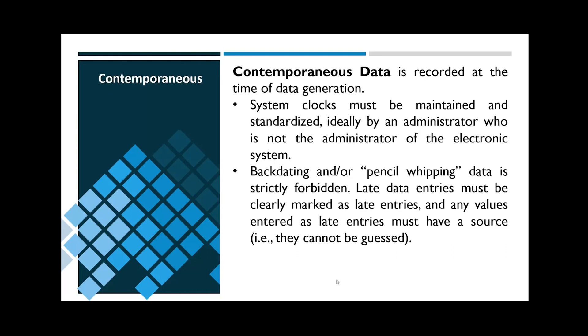Contemporaneous data is recorded at the time of data generation — that means no backdating data, no pencil-whipping. Late data entries must be clearly marked as late entries, and the values entered must have a solid source, such as historization. No guessing or assuming. Another requirement for contemporaneous data that's often overlooked: your system clocks need to be maintained and standardized, ideally by an admin who isn't the admin of the system currently in use. That extra degree of separation is just another level of protection.